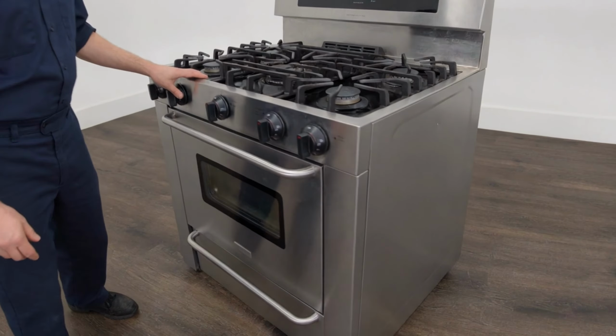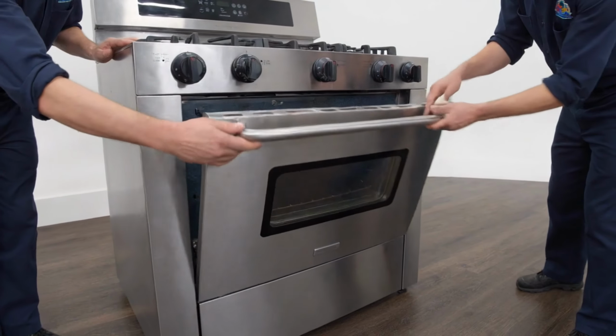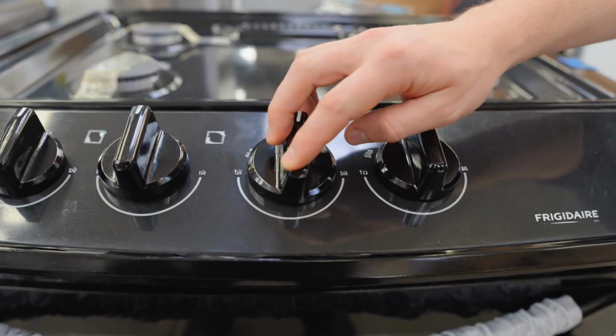In the workshop, we explained that this code appears when the oven receives signals it can't properly interpret or detects inconsistencies in its operation. Continuing with what we see day to day, some customers say, the oven turns on, but it doesn't heat properly and then the error appears. In these cases, the first thing we check is the main control board because it's responsible for coordinating all oven functions. We technicians usually say, if the board receives confusing information, the system protects itself and shuts down.